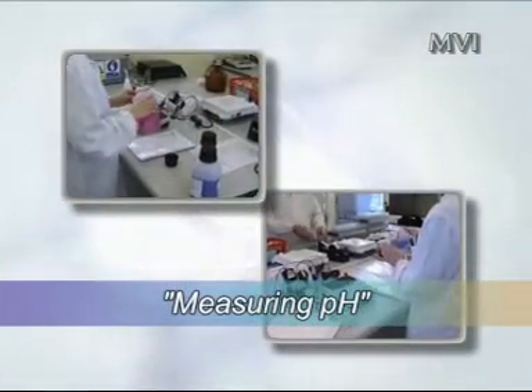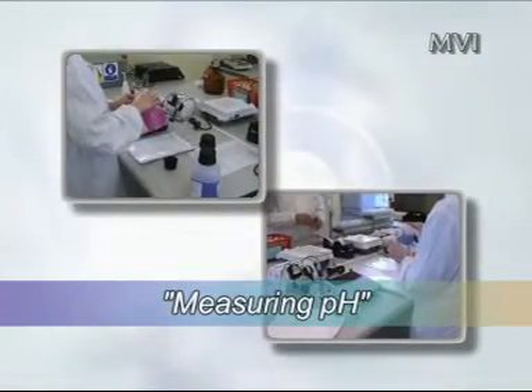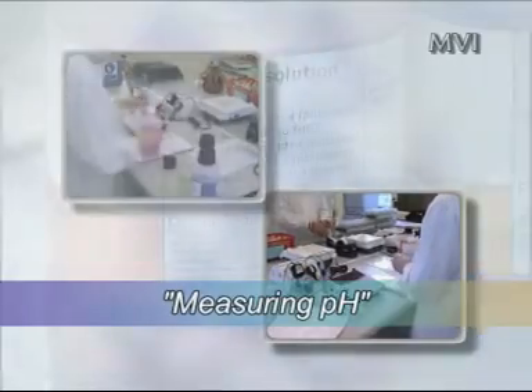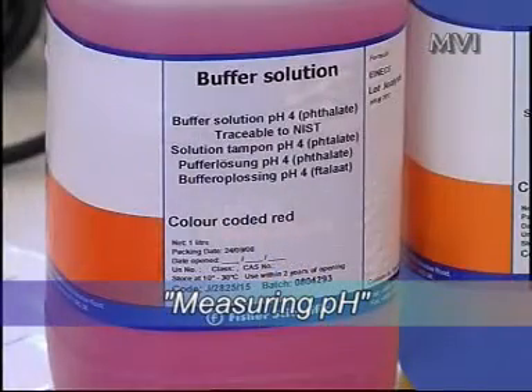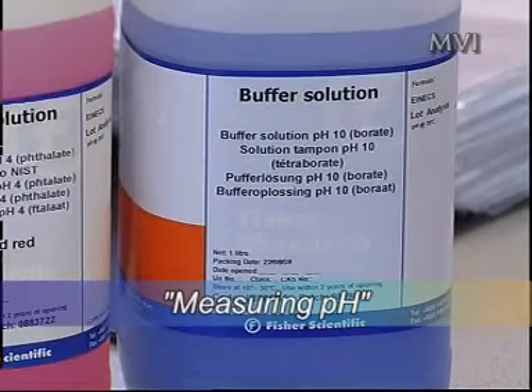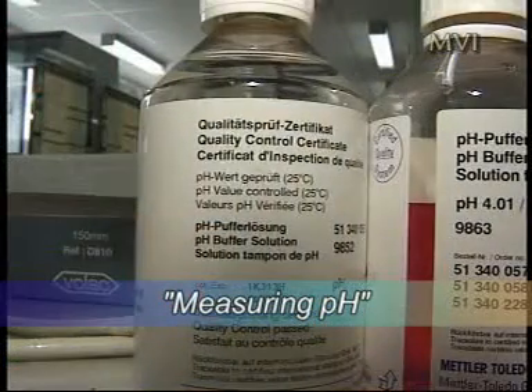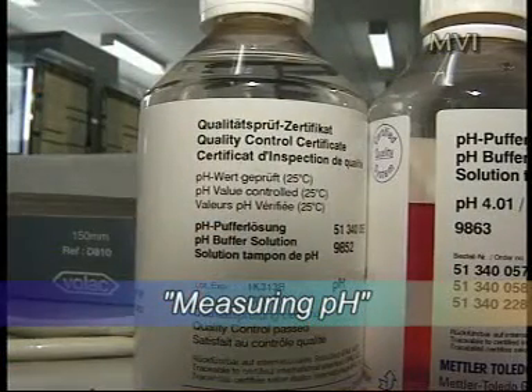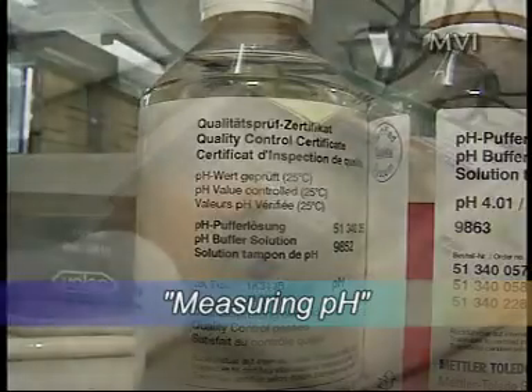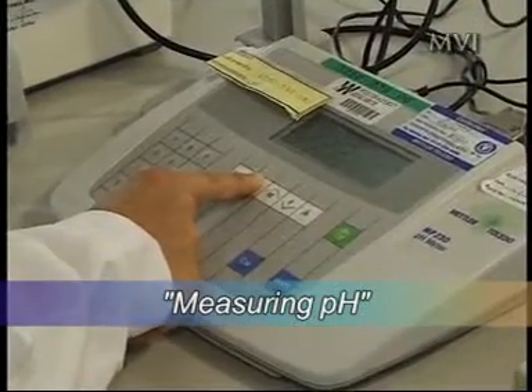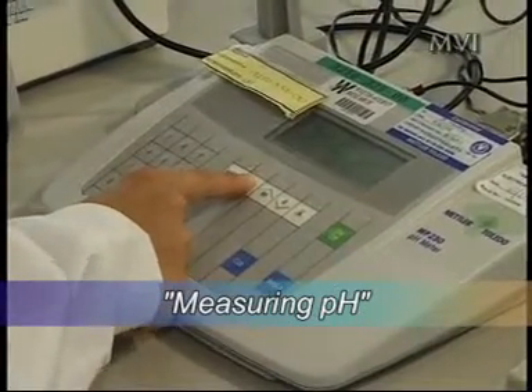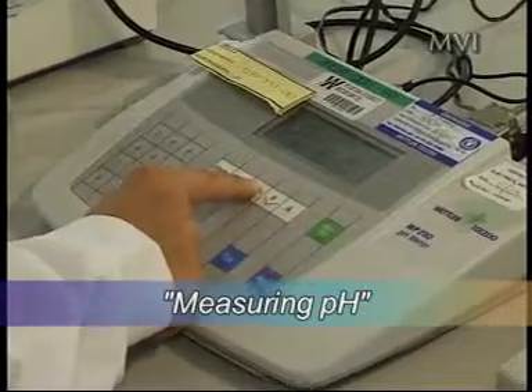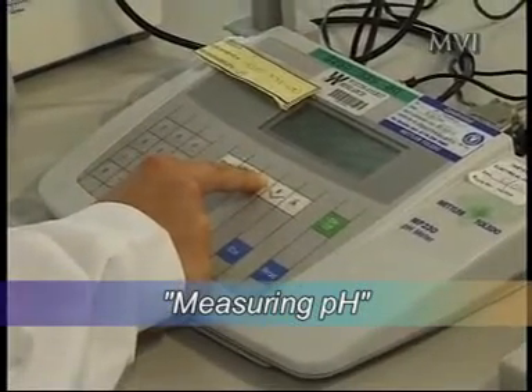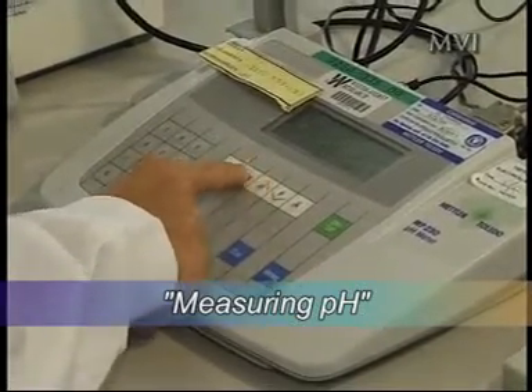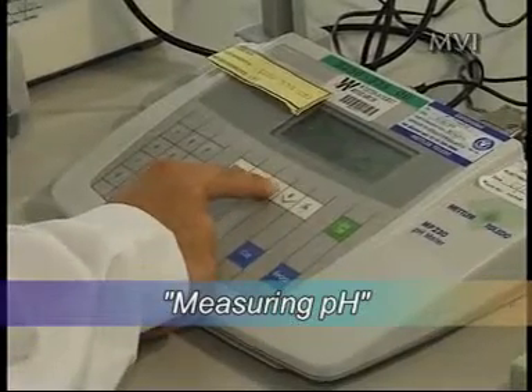If it is needed, this is a true calibration and is done against two standard buffers. For general purposes, pH 4 and pH 10. These buffers are available with certificates of conformance from all reputable laboratory supply houses. A typical pH meter has one calibration control to set the meter reading equal to the value of the first standard buffer, and a second slope control, which is used to adjust the meter reading to the value of the second buffer.